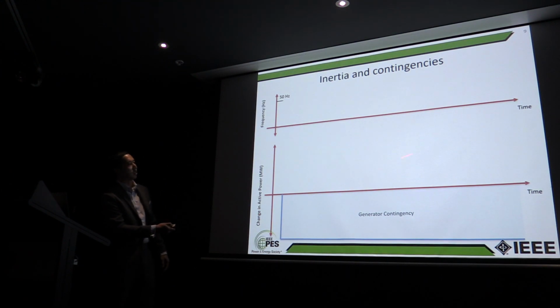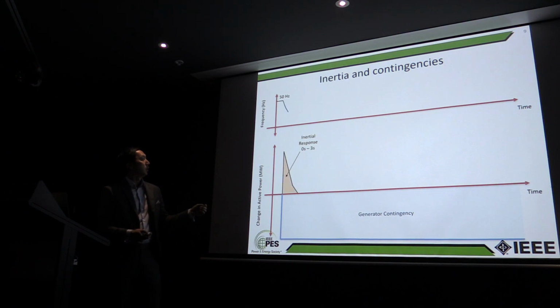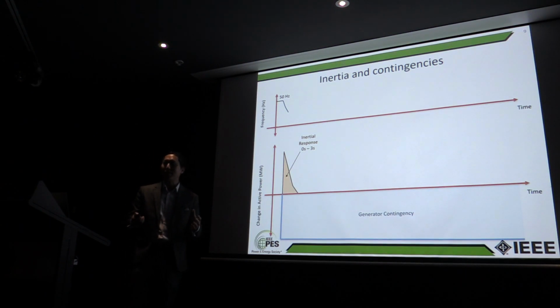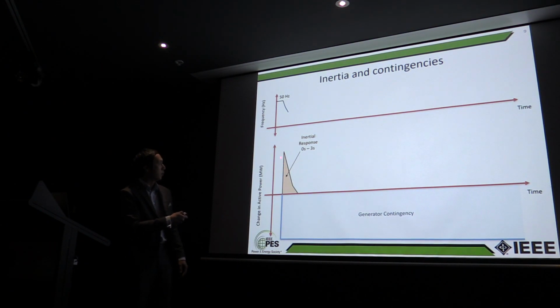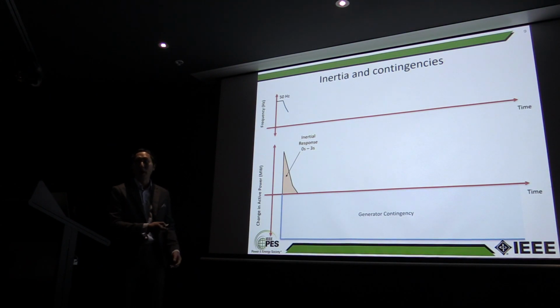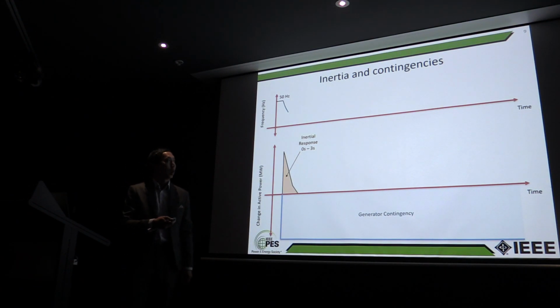So here we have on this axis the change in active power, and this is just time. At some point we're humming along at 50 hertz, and then all of a sudden, we've lost all this generation. This is a negative change here. This could be like 200 megawatts. We've just lost that in a split second. So what happens in the first instant after we lose a generator? The inertial response comes in. This is where all the other generator masses come in and supply that energy. So that power there is the same as that power there. It's being supplied, but as a result, frequency starts going down. That's what we just described before.